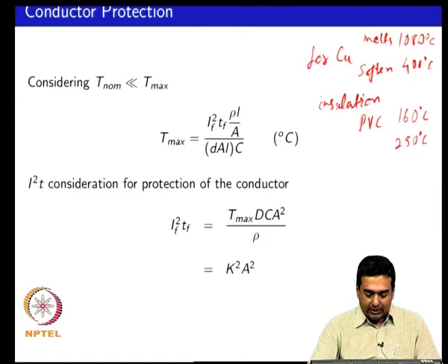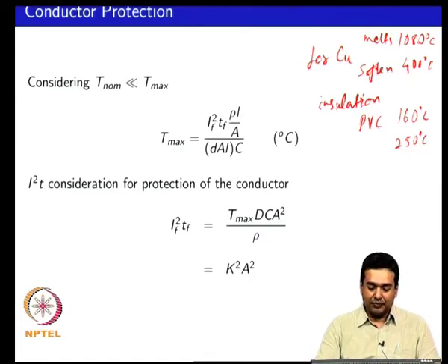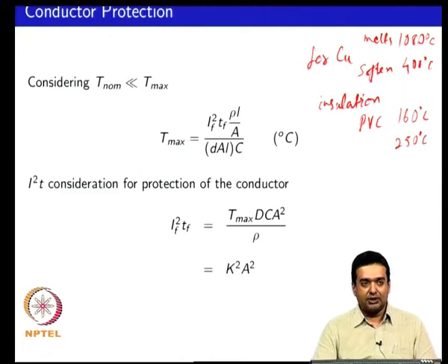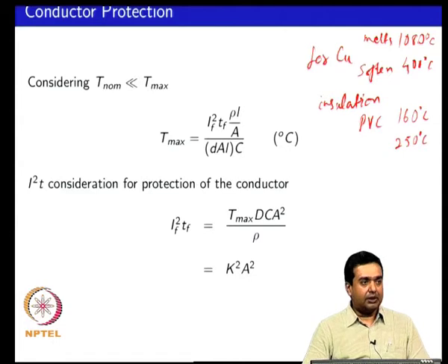So, with that we also need to keep in mind the assumptions that you have. We are assuming in this particular case all the heat that is deposited is going into raising the temperature. So, we are neglecting all cooling effects. Given the short time duration over which this is happening, that may be reasonably true, but if your fault is occurring for a much larger time duration, you may have to consider factors for your cooling effects, which might change the T max.